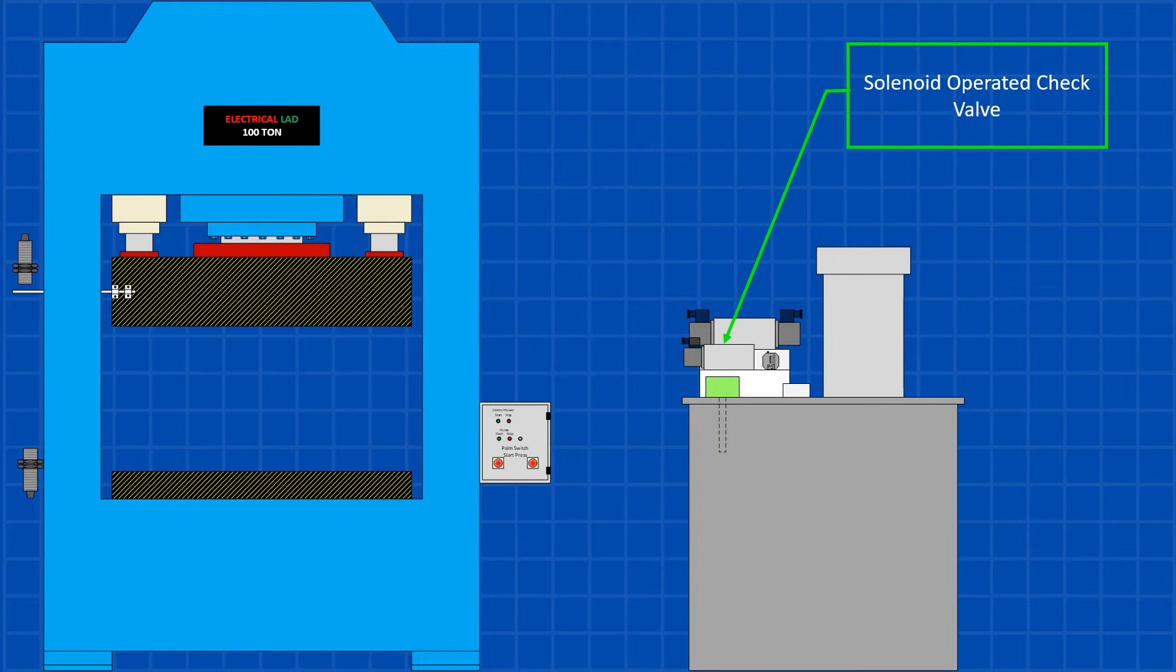The press also uses a solenoid-operated check valve as a safety feature to prevent it from drifting down when in the up position. The solenoid is only energized during the downward movement. Keep in mind, a real press has many other valves, like counterbalance and flow control valves that I won't cover in this example.